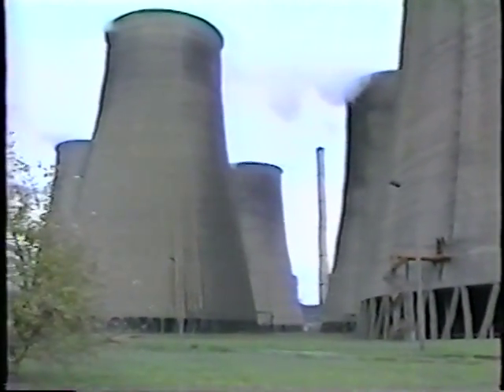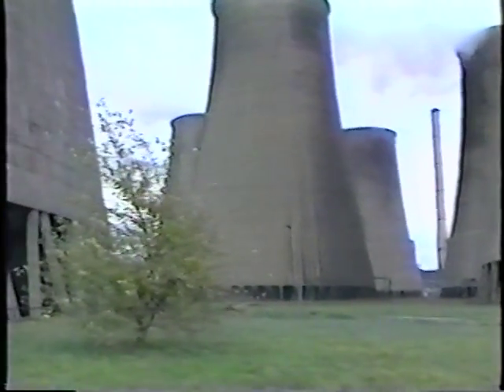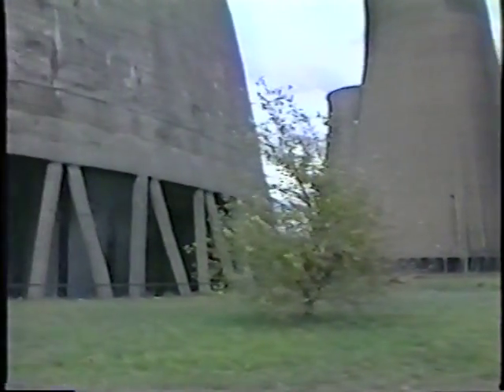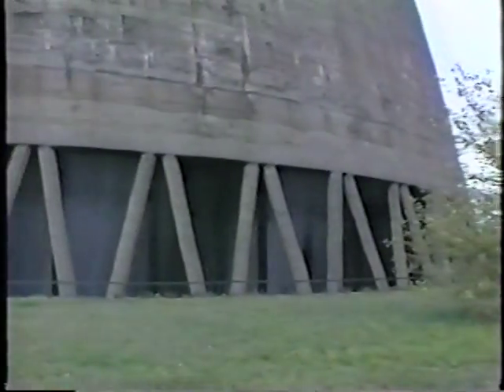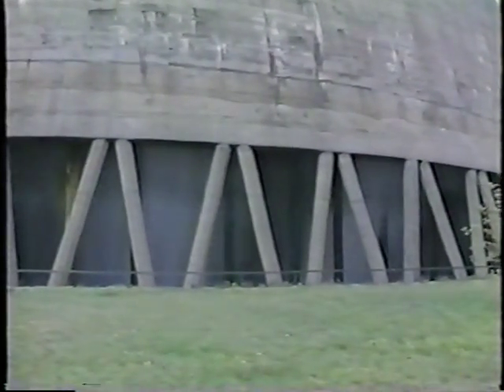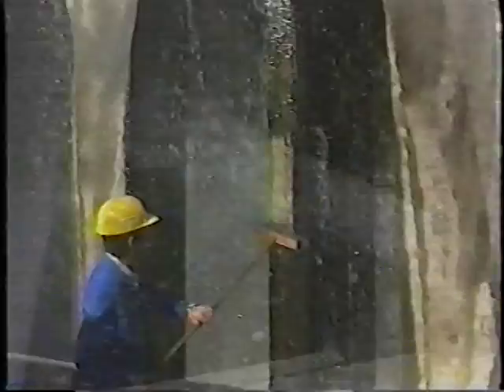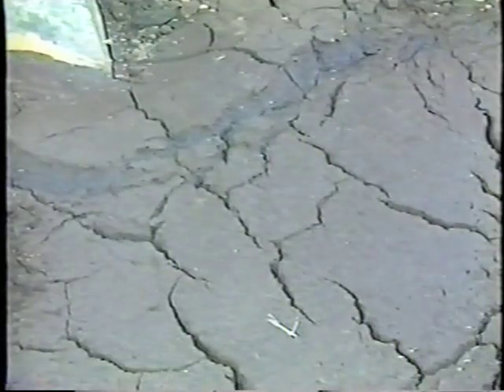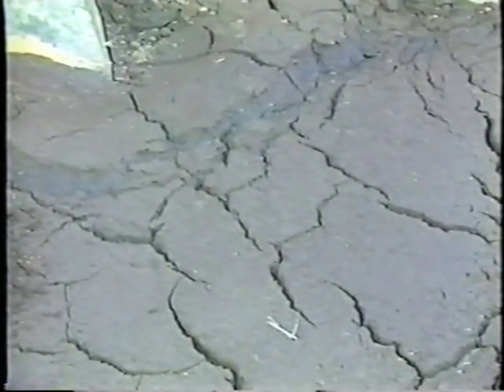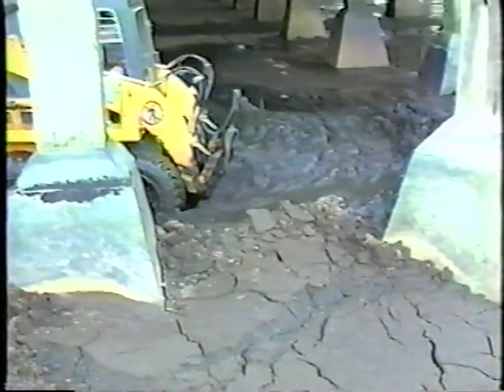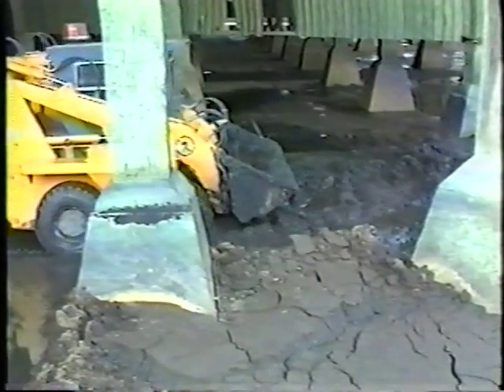In cooling tower power stations, we come across quite specific types of debris, such as bits of concrete, fragments of internal parts, dust from the air, alkaline scaling, and, depending on the time of year, grass or leaves. Algae and fibers are particularly difficult to remove and cause corrosion and erosion within the system. The extent of all this contamination is clearly demonstrated by this cooling tower pond. Result: unplanned plant shutdown.